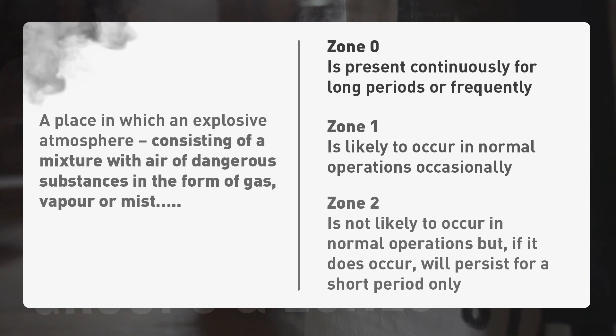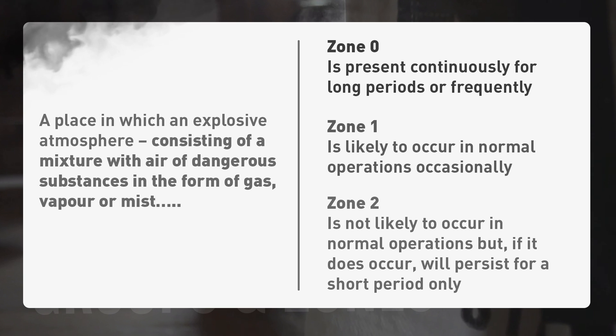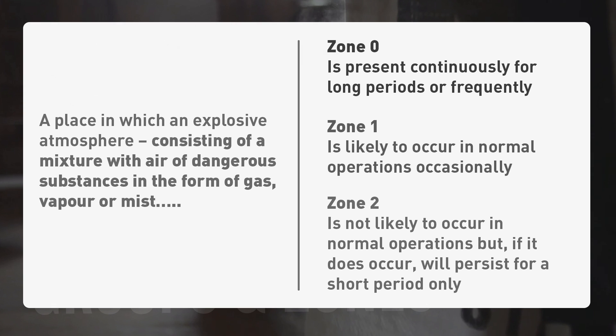Whether the areas are classed as zone 0, 1 or 2 depends on the likelihood that the explosive environment will occur and, if it does occur, the frequency of its occurrence. For example, in the case of zone 2, it is considered unlikely that the explosive environment would occur in normal operation, and if it did, it would only be for a short period.